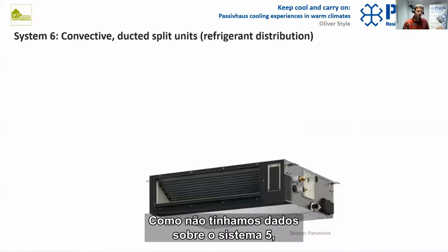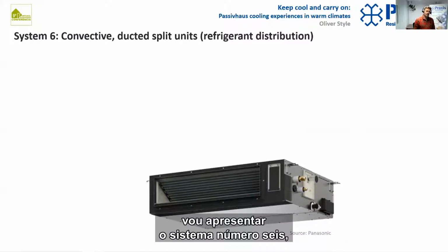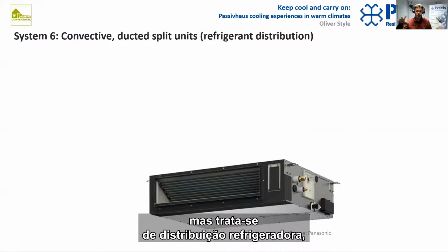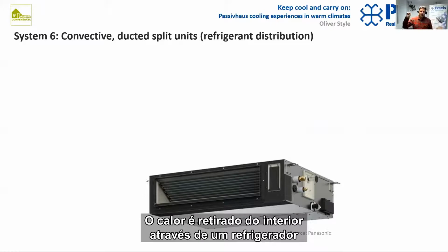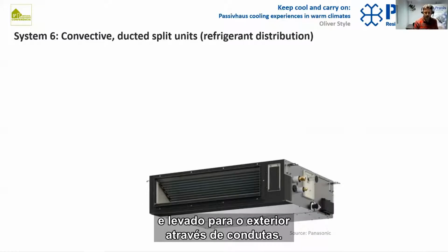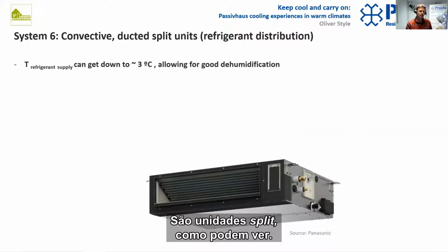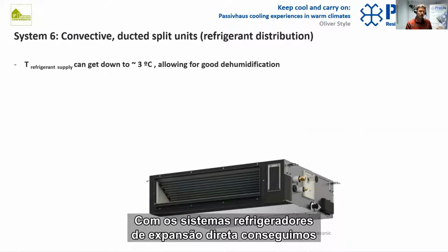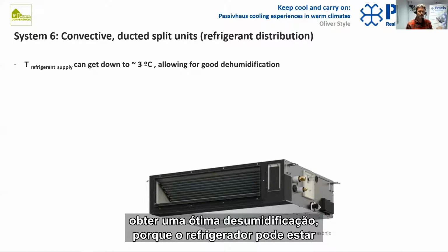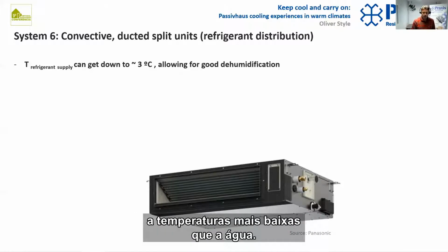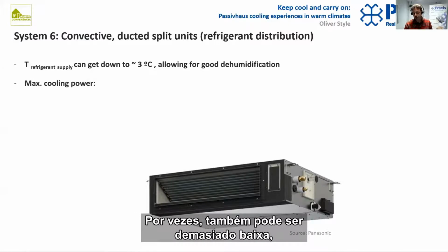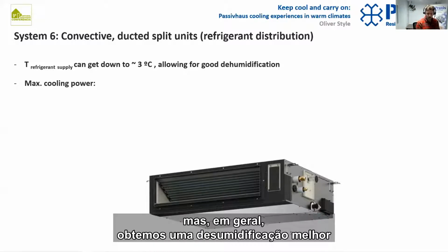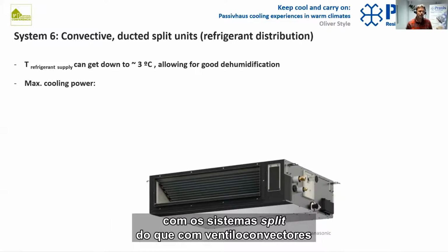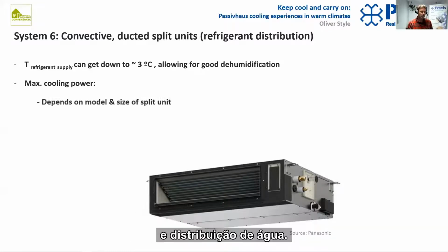So system number 5, we didn't have any monitored data for, so I'm just going to present system number 6 here, which is a similar technology, but here we're dealing with all refrigerant distribution. So we're just doing air to air. Heat is moved from the inside to a refrigerant and then taken outside with ducted split units, as you can see here. So with refrigerant direct expansion systems, we can get really good dehumidification because the refrigerant can be at a lower temperature than water. Can also be sometimes too low, but we can generally get good or better dehumidification with split systems than we can with fan coil and water distribution.